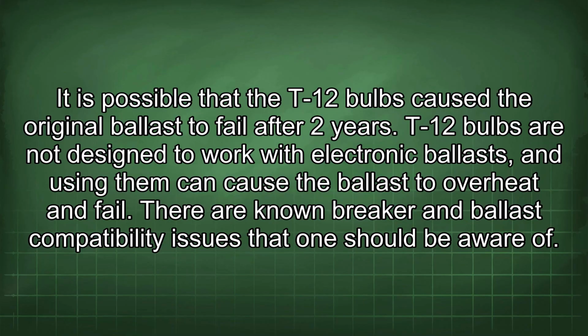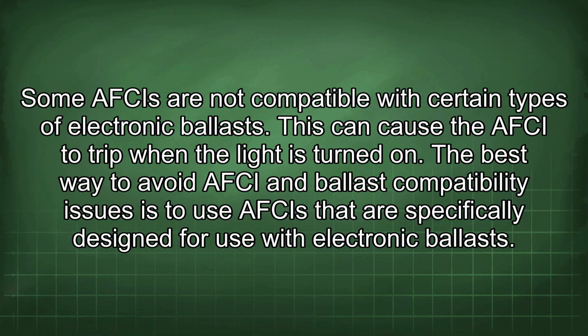It is possible that the T-12 bulbs caused the original ballast to fail after 2 years. T-12 bulbs are not designed to work with electronic ballasts, and using them can cause the ballast to overheat and fail. There are known breaker and ballast compatibility issues that one should be aware of. Some AFCIs are not compatible with certain types of electronic ballasts. This can cause the AFCI to trip when the light is turned on.